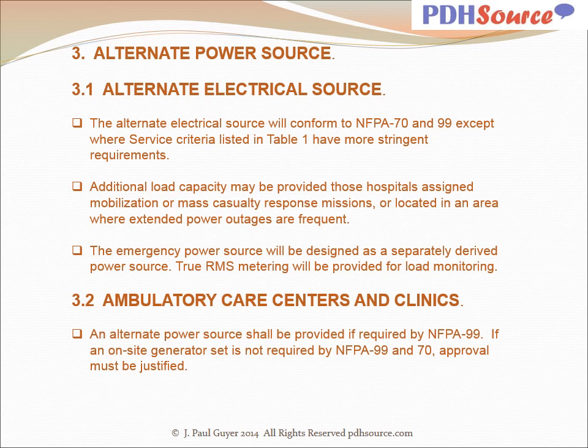Additional load capacity may be provided to those hospitals assigned mobilization or mass casualty response missions or located in an area where extended power outages are frequent. The emergency power source will be designed as a separately derived power source. True root mean square, RMS, metering will be provided for load monitoring. With regard to ambulatory care centers and clinics, an alternate power source shall be provided if required by NFPA 99. If an on-site generator set is not required by NFPA 99 and 70, approval must be justified by the owner.